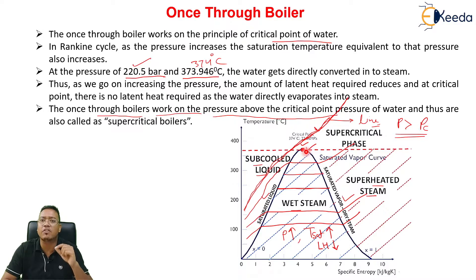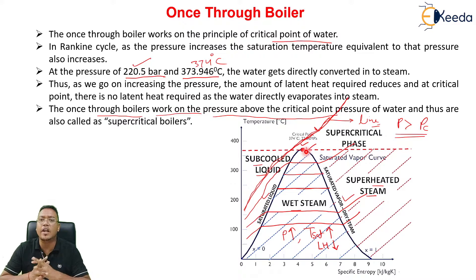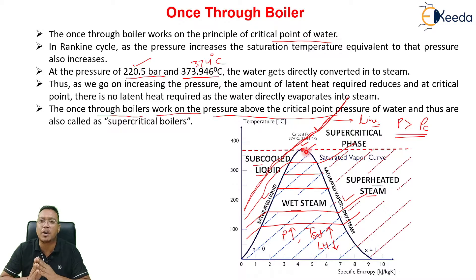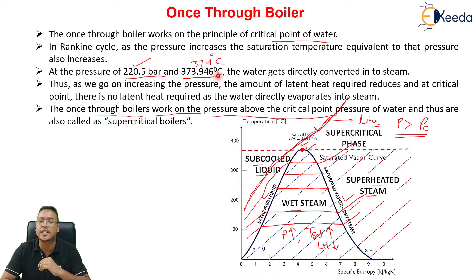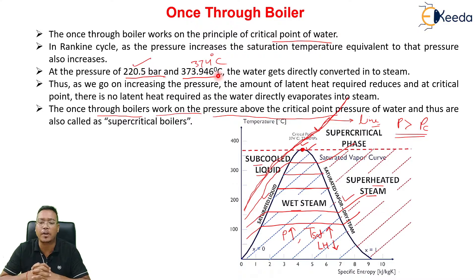The supercritical boiler will work at a pressure beyond the critical point pressure. The value for critical pressure is 220.5 bar, or we can say 221 bar. The temperature is 373.946 degrees Celsius, or approximately 374 degrees Celsius. These are the conditions — pressure and temperature values — at the critical point.